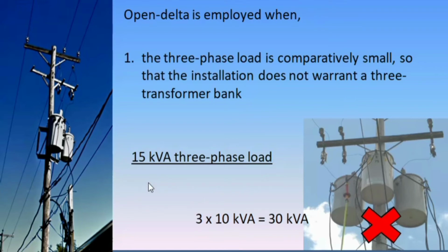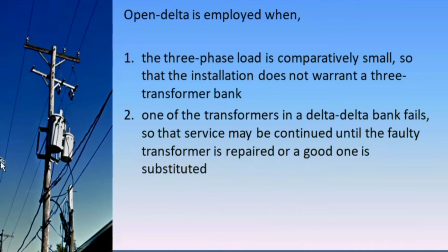But of course, the capacity of an open delta will not be 2/3 of that of a closed delta system. We will discuss that later. Let's go to the next application of open delta. It is employed when one of the transformers in a delta-delta bank fails, so that service may be continued until the faulty transformer is repaired or a good one is substituted. So it is very clear from what we've just read, open delta connections are used in emergency conditions. At least the service is continued despite one of the transformers failing.